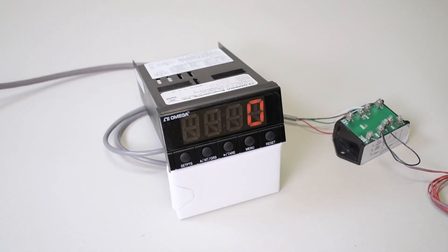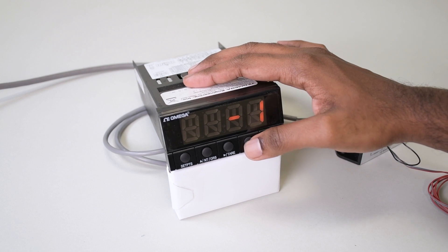Now that we've calculated the sensitivity, it's time to push some buttons and get this meter programmed. Once you're done with the wiring and you've turned on the DP25B-S unit, press the menu button once.